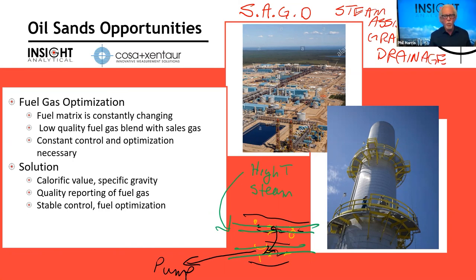And we want to do that with the minimum of environmental emissions. So now we want to make sure that burner runs really well. But when we do this, we also get some gas that comes back with this stuff. We'd like to burn that gas too, but it's going to vary in composition. So when we get over to the steam generator, which is really just a big boiler, just like we would have at a power plant, our fuel matrix is always changing.